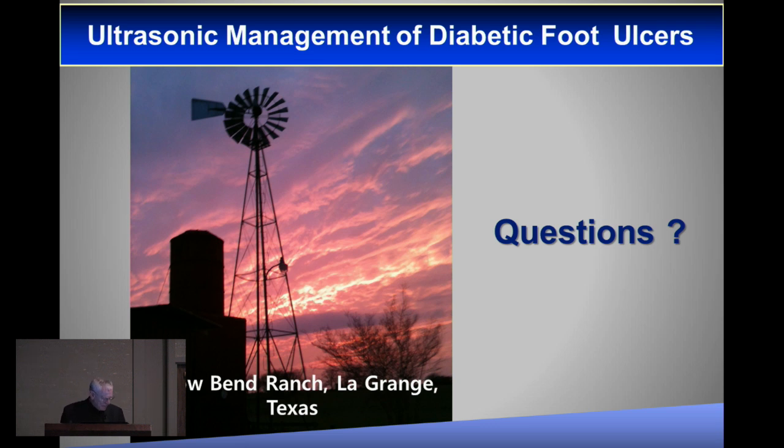Yes. So this thing preferentially destroys necrotic tissue. Is that right? Yes. And it will also destroy bone. Okay. So you can use it like you would a burr or something, except that it operates preferentially. And you've got a cannula there that sucks out the damaged tissue that you destroyed. Right? Yes, that's it. And then you've got bleeding that's left over, and that's what you see as your blood flow. So the underlying vasculature to the foot, say, is unaffected. It's just the local area that you're treating where they've got the ulcer.